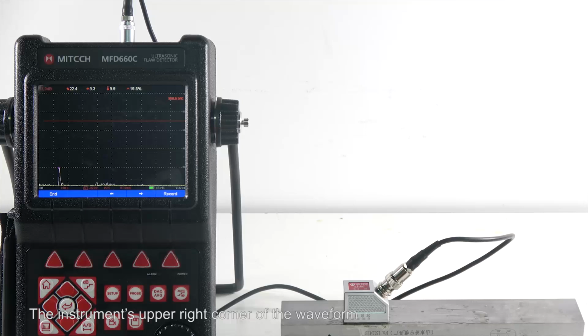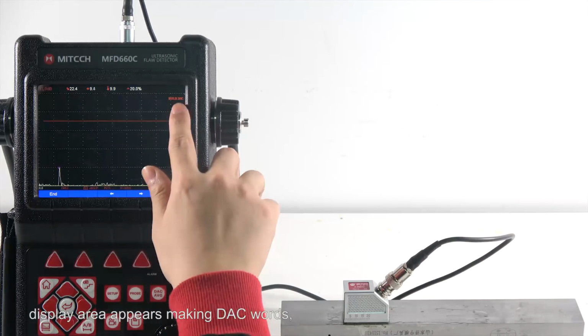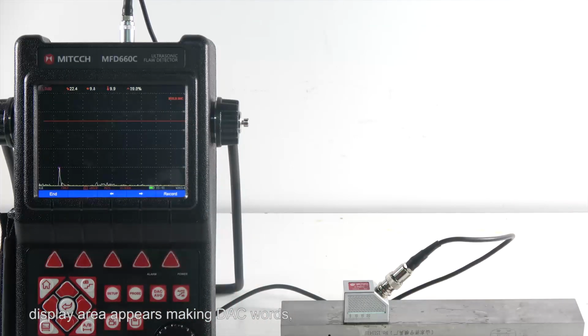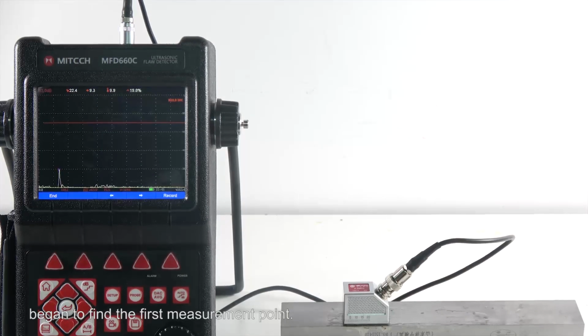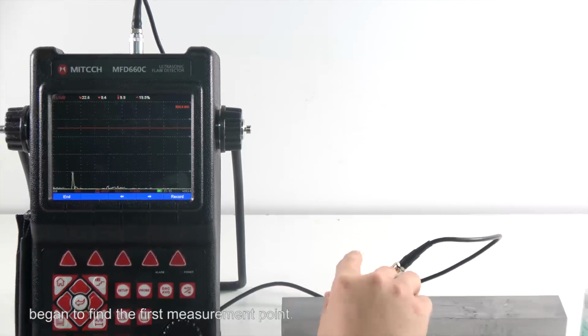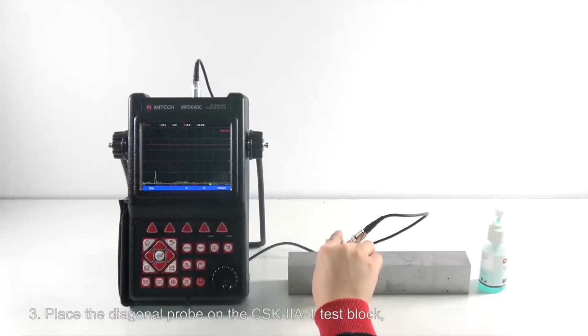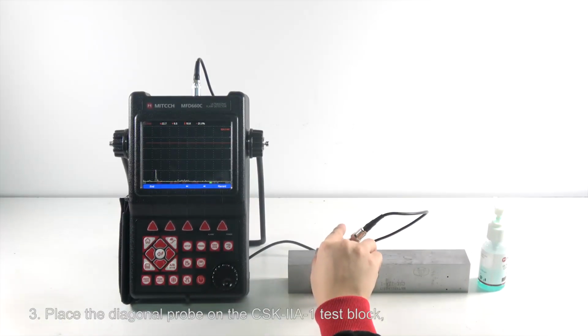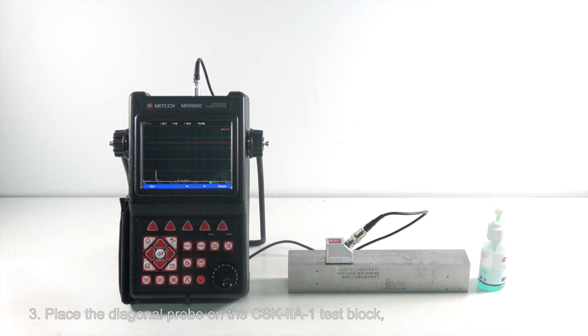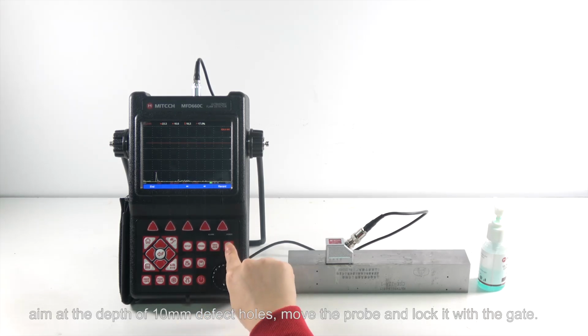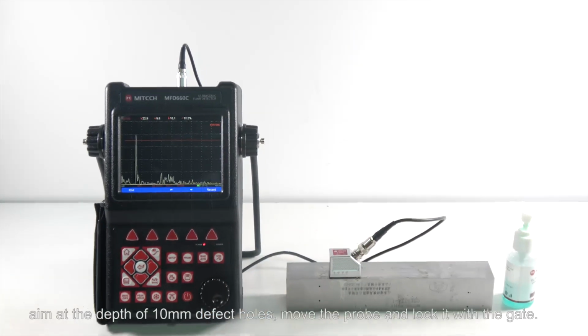At the upper right corner of the instrument's waveform display area, "DAC" appears, which represents that it has entered the curve-making state. Begin to find the first measurement point. Place the oblique probe on the CSK2A1 test block, aim at the defect hole at a depth of 10 mm, move the probe and lock it with the gate.